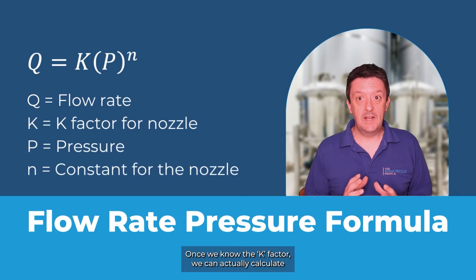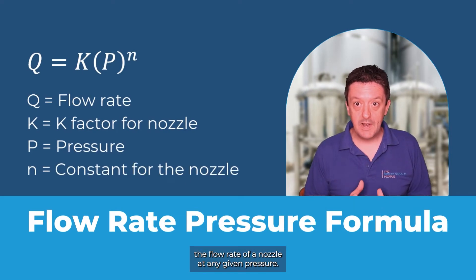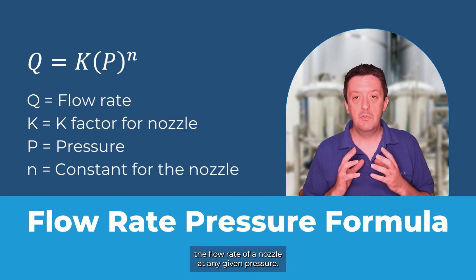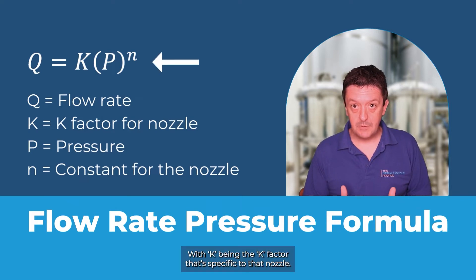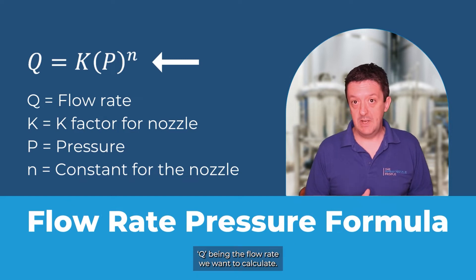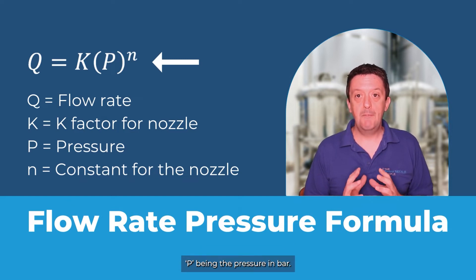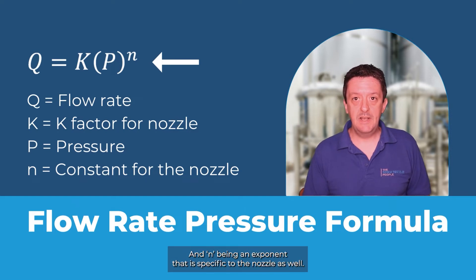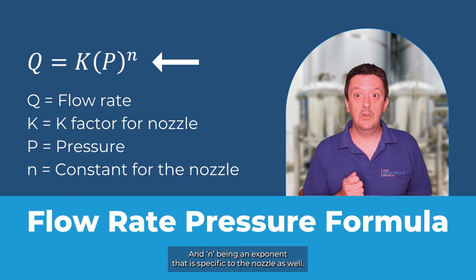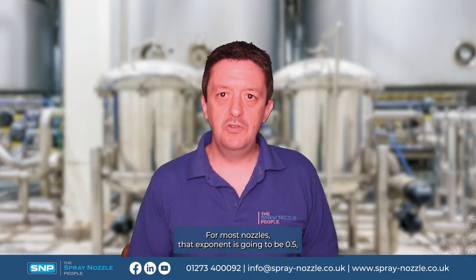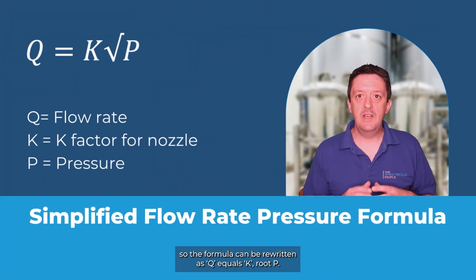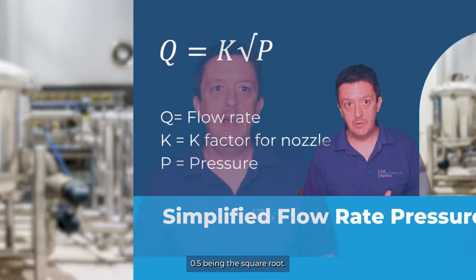Once we know the K factor, we can actually calculate the flow rate of the nozzle at any given pressure. We can use this formula here, with K being the K factor specific to that nozzle, Q being the flow rate we want to calculate, P being the pressure in bar, and N being an exponent that is also specific to the nozzle. For most nozzles, that exponent is going to be 0.5, so the formula can be rewritten as Q equals K times the square root of P.